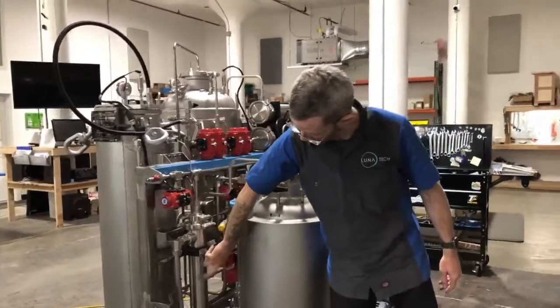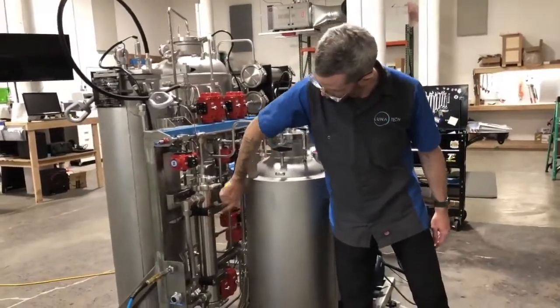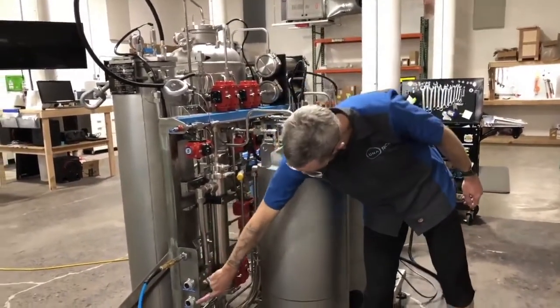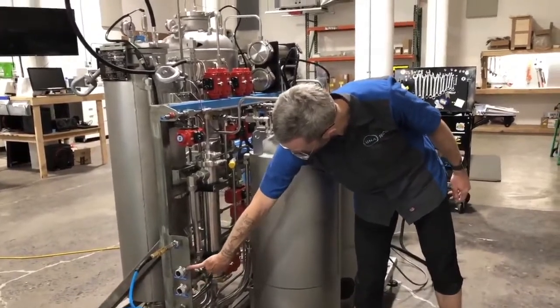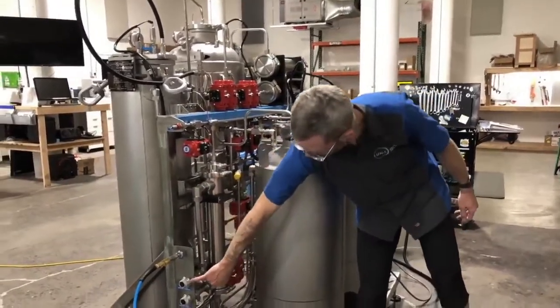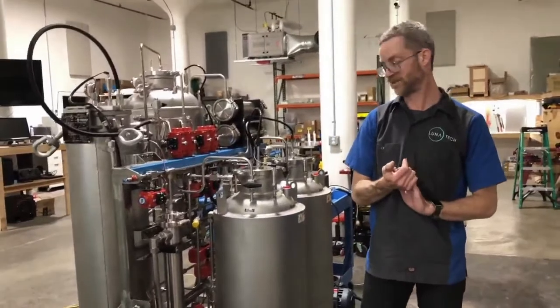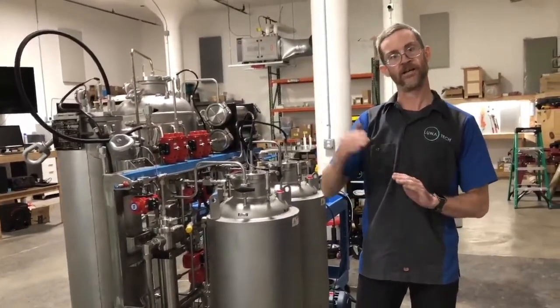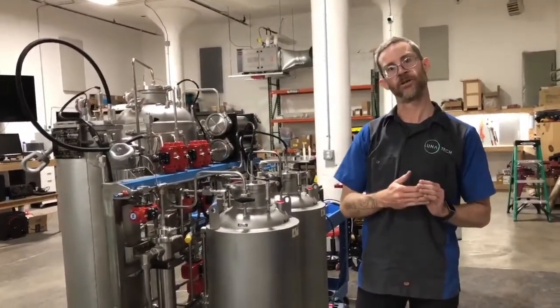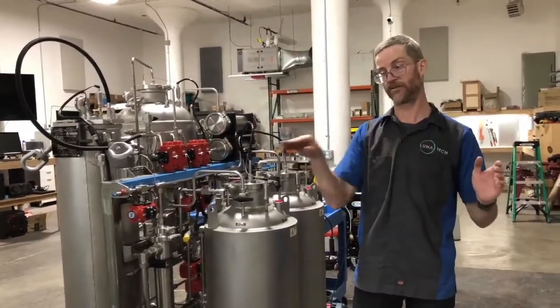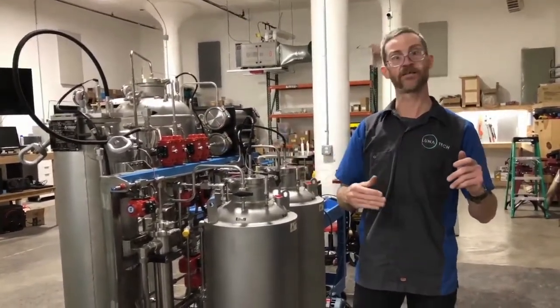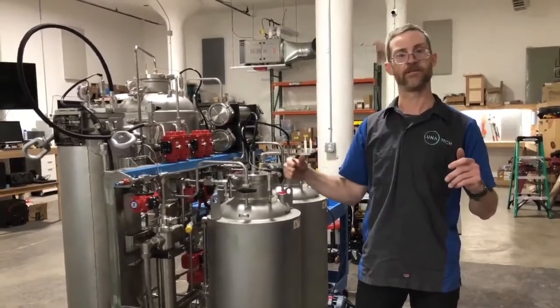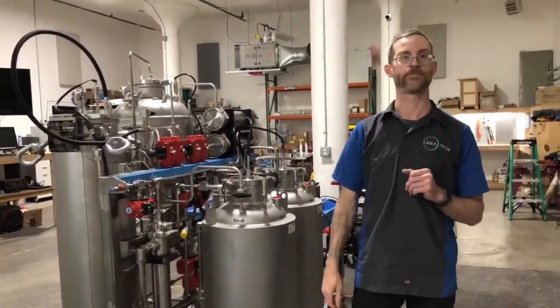And then the condenser here, this heat exchanger, since it is such a short circuit, this is the input, this is the output, just goes through here. We test that one to 80 or 75 pounds of pressure. If there is any pressure loss over 30 minutes for any of those tests, the test fails, we find the leak, fix the leak, and test it again. All right.